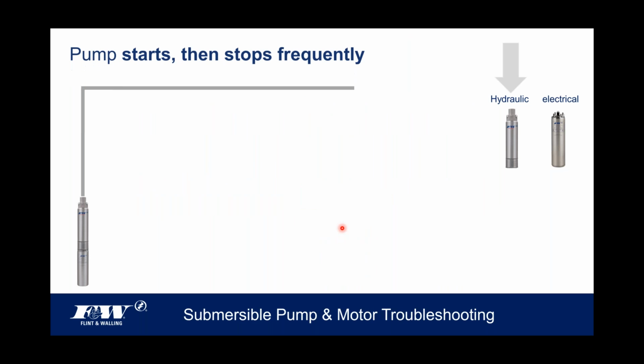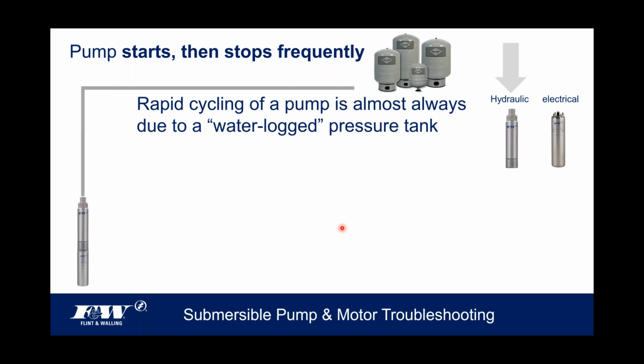Okay, so here's this next slide, and this is getting to where I was going. The pump starts and then stops almost immediately. All right, it starts and stops frequently. It's called rapid cycling. Almost every time you open a faucet, the pump comes on, shut the faucet, the pump shuts off. It's like, well, wait a minute, why is that pump coming on and off every single time I use water? Rapid cycling of a pump is almost always due to what's called a waterlogged pressure tank.